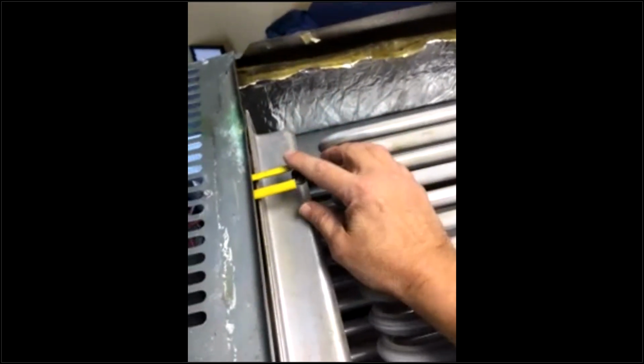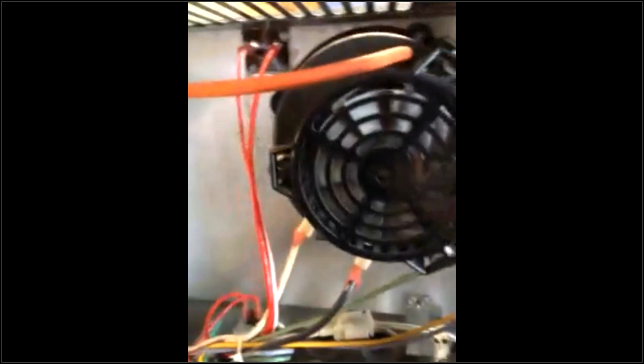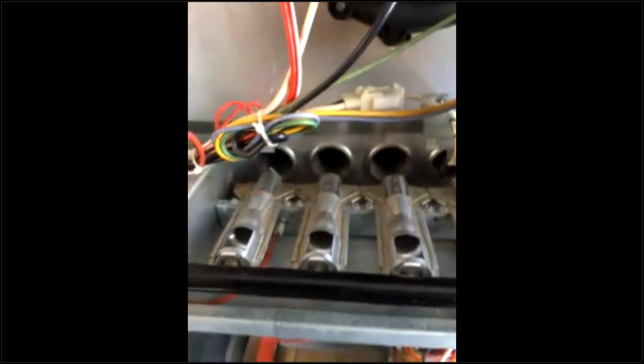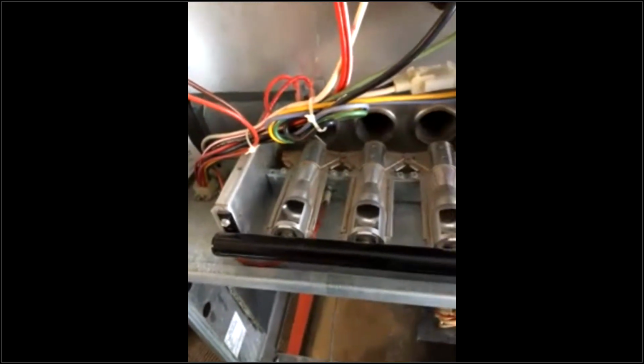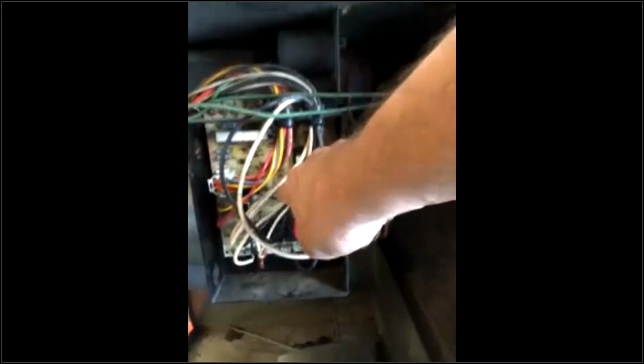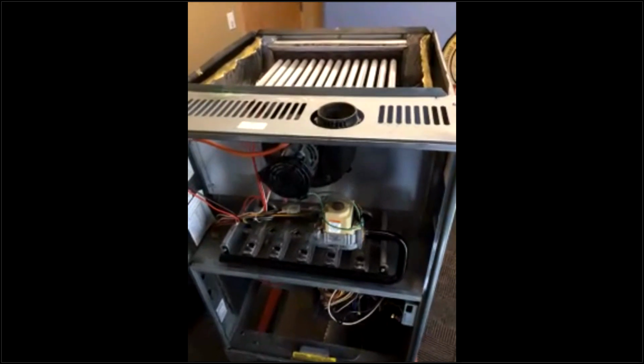Here's another switch here, a temperature switch. If this gets too hot, there's something wrong. And this switch is connected here, there, and it's connected to the electronics. It'll shut everything down if it's not safe. There's that fan switch. It's supposed to be there. There's a control board and little light bulbs indicating error codes. And there's a blower fan from below and from the side, and that's where the air filter would be located right here. So those are all the parts of this gas furnace.